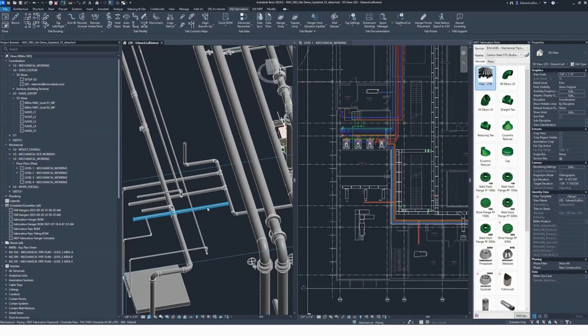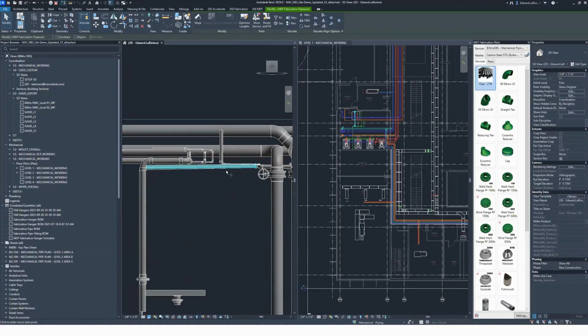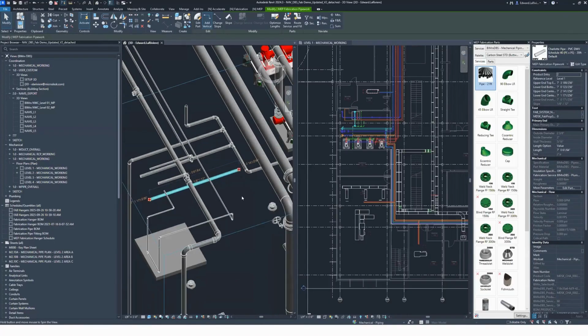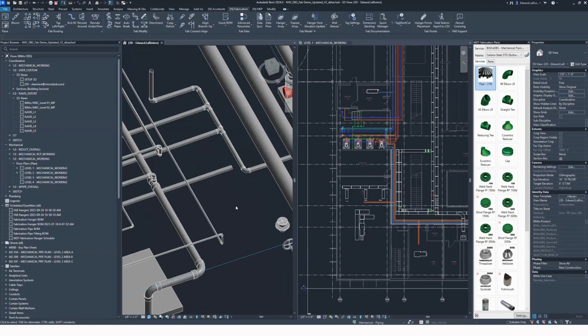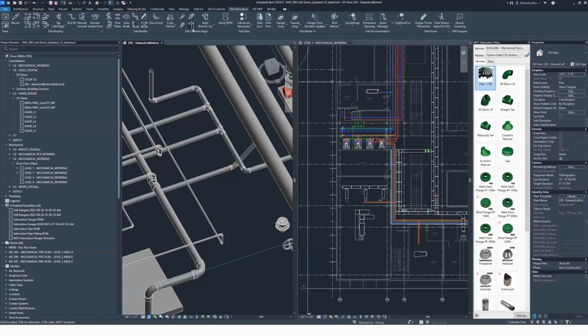Well, this is the magic of these 3D views. As long as you're hitting those left planes, it's the exact same thing as a section. So do your coordination, move your elements around, make sure your stuff fits, and do it all in that same view the entire time you're modeling. Let Revit work for you. Don't struggle trying to find your items in all those different views. And you know what? I don't even want to draft over there. I'm going to leverage one of these elbow up 45 tools to go ahead and give me that run. And we're right back to square one with that aligned branch, sliding the fitting along the pipe and allowing me to connect.